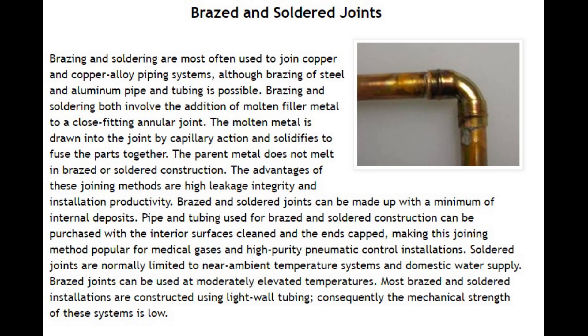Pipe and tubing used for brazed and soldered construction can be purchased with the interior surfaces cleaned and the ends capped, making this joining method popular for medical gases and high purity pneumatic control installations. Soldered joints are normally limited to near ambient temperature systems and domestic water supply. Brazed joints can be used at moderately elevated temperatures. Most brazed and soldered installations are constructed using light wall tubing, consequently the mechanical strength of these systems is low.